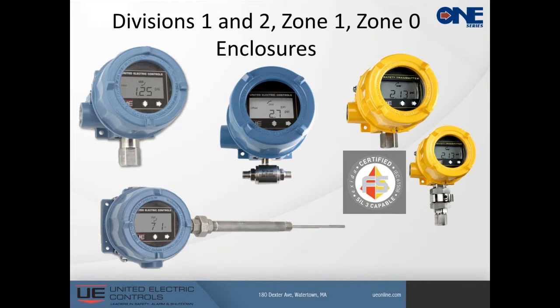So really where we are right now in this whole family of the 1 Series, this really rounds out the capability of the Blue product, from static pressure differential to temperature, from just standalone as a switch, standalone as a HART-enabled transmitter, or HART-enabled transmitter plus 2 switches. We have that capability in this enclosure. And then, of course, we round it out with the ever-increasing popularity of our SIL 2 certified, SIL 3 capable safety transmitter. And we can talk about that with your questions if you have any. But that product is doing very well for us.